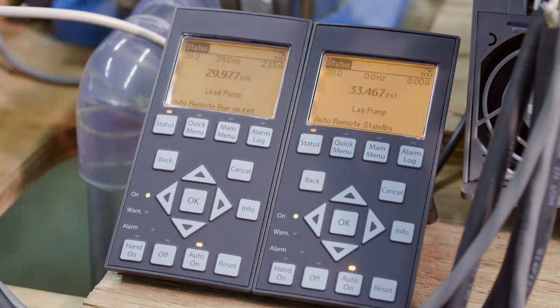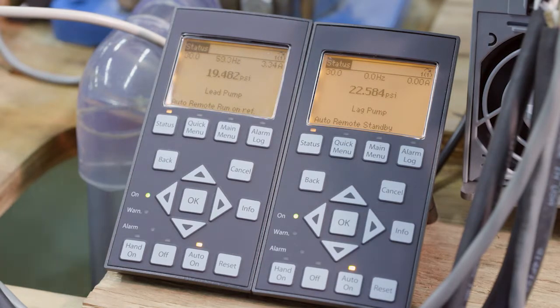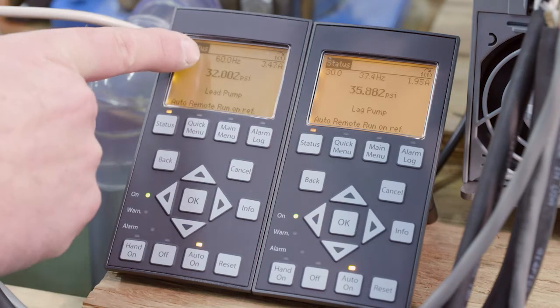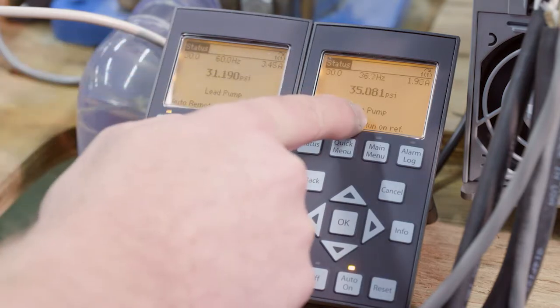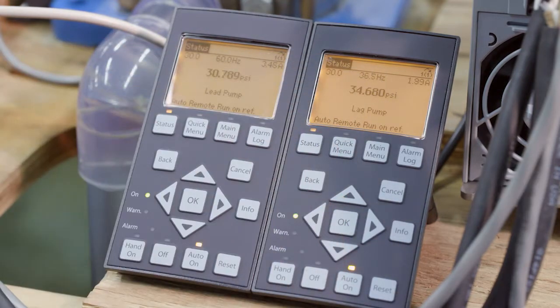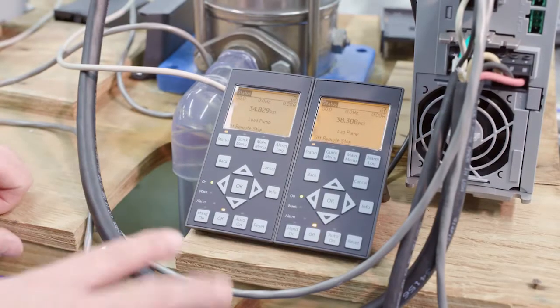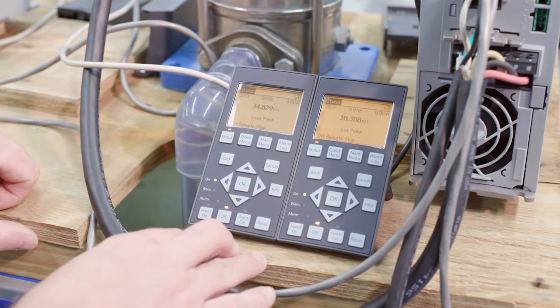So let me open up the valve. We can see the lead pump ramping up. So this is part of the staging process here, and it's calling for pump 2 to come on. So notice that our lead pump is full speed, 60 hertz, and our lag is 36, 37. So that is multi-master, multi-control. Pump 1, again, a duplex, full speed. Pump 2 is varying. So that was multi-master, multi-control. Very quick overview of that.